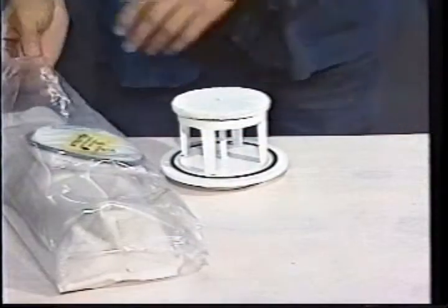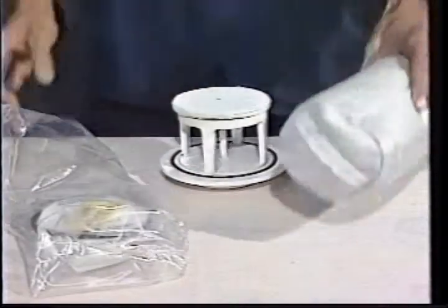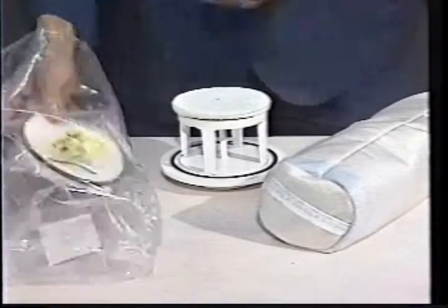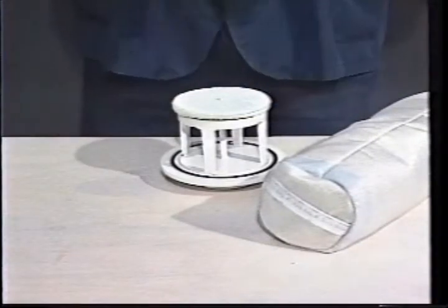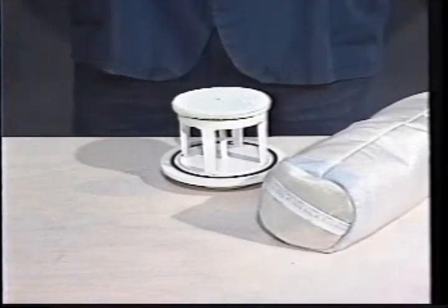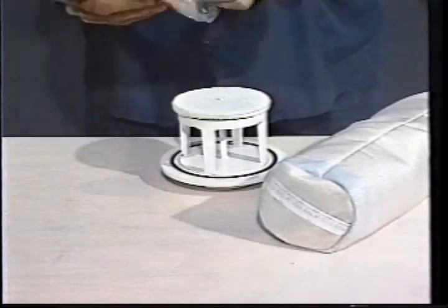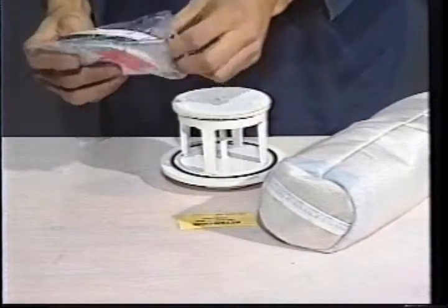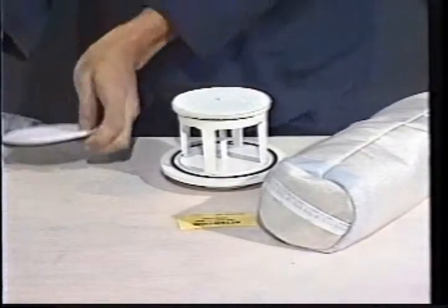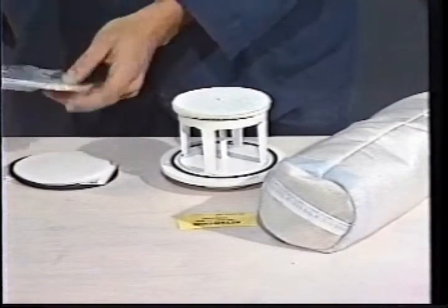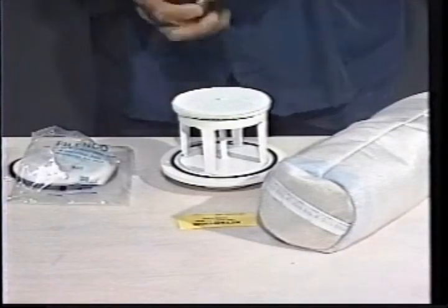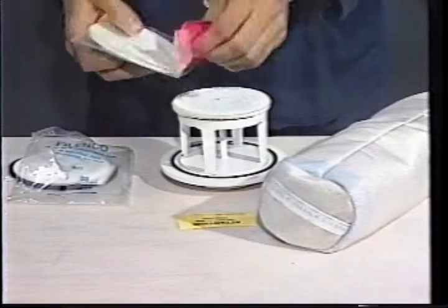When it's necessary to replace filter elements, Filenco offers a 5-part filter fix-it kit, which includes a new bag of desiccant, 2 sets of filter discs. The first, for units made before 1993, are solid and sandwiched between 2 stainless steel screens. The second fits units manufactured after 1993. They have holes in the center, so the lower screen can be screwed to a threaded stud. This firmly secures the filter discs to the cover and spacer, or spacer alone.